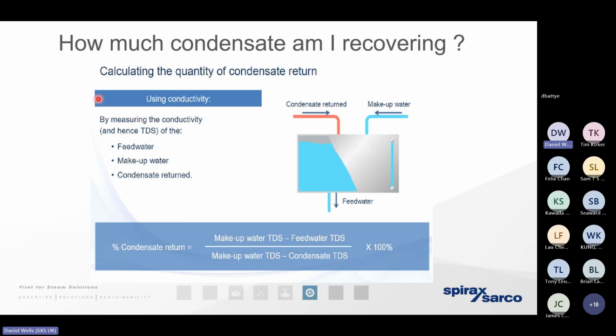We can only really meter condensate when it's in its single phase liquid state. It's far, far more efficient to actually monitor the condensate return chemically. The reason is boiler guidance best practice. It dictates that we need to monitor the chemical composition of the water in three key areas. It's the chemical composition of the condensate that's being returned to the hot well, any makeup water that's coming from the water treatment plant to make up any losses through inefficiencies like failed steam traps, and then the chemical composition of the feed water as it's taken into the boiler. So if we're monitoring the chemical composition of the water in those key areas, which boiler guidance best practice dictates that we need to do on a daily basis, well, we can use the formula shown at the bottom of the screen to help us calculate a ratio or a return percentage.